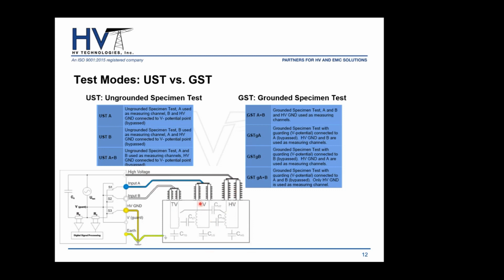So we have a high, low, and a tertiary winding. For the interwinding capacitances, you will use the ungrounded specimen test, which makes a lot of sense. You have some that go to ground, you use your GST, and others that do not go to ground and will be measured using your UST, or ungrounded specimen test.